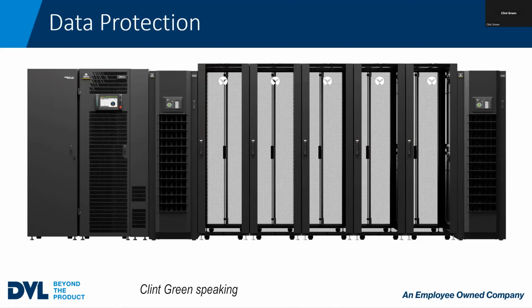Then let's talk about data. Do we need that uninterruptible part that Gordon mentioned? A generator is going to take on average about 10 to 15 seconds to start and connect to the building load. During that portion, you have a gap, a glitch in your power, a little blurb where there is no power before the generator starts up. So maybe we need to add a UPS on it.